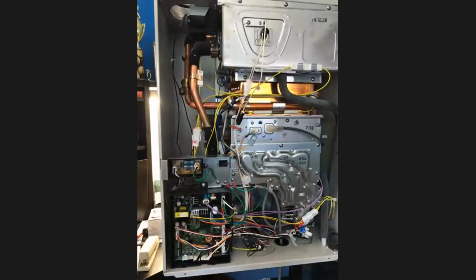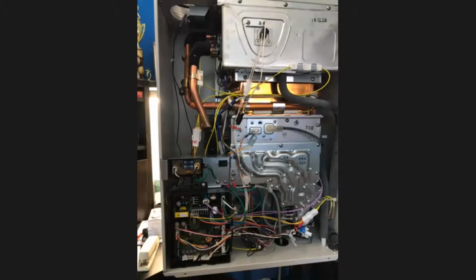What's another thing we might want to look at? Our gas piping, making sure we have adequate gas supply pressure. The real difference between a tank type and a tankless is the amount of gas used in a period of time. Like I said earlier, if I heat 100 gallons of water, I use the same BTUs, I'm just using it a lot faster because I produce it quickly. My recovery rate is fast.